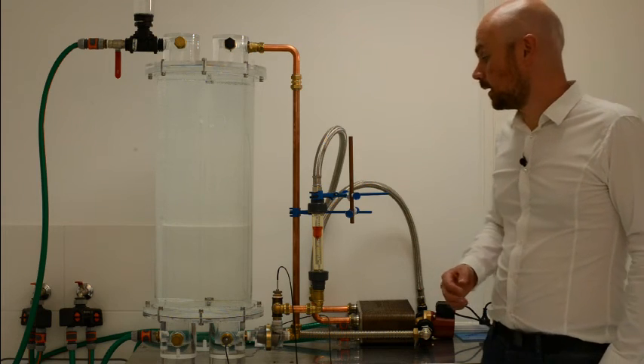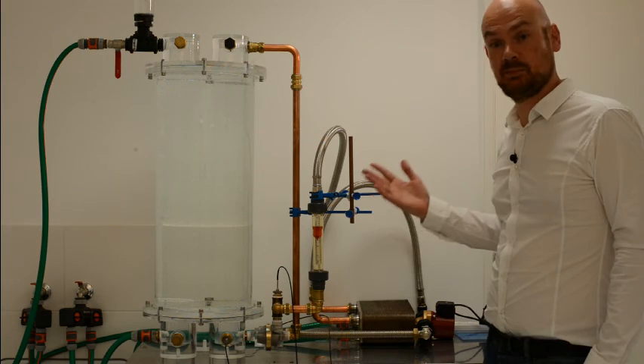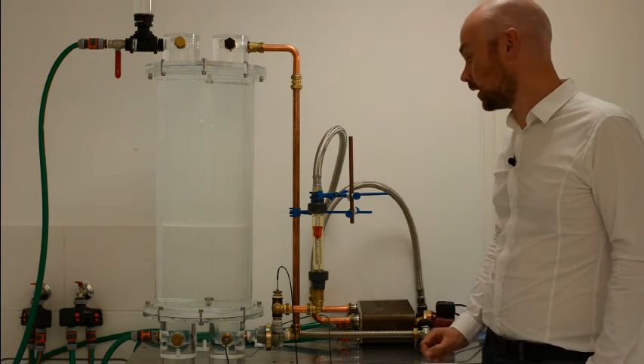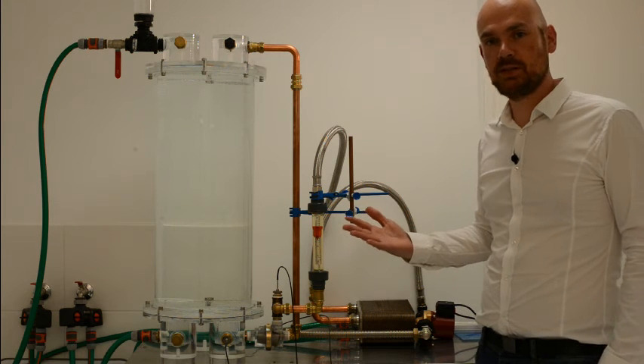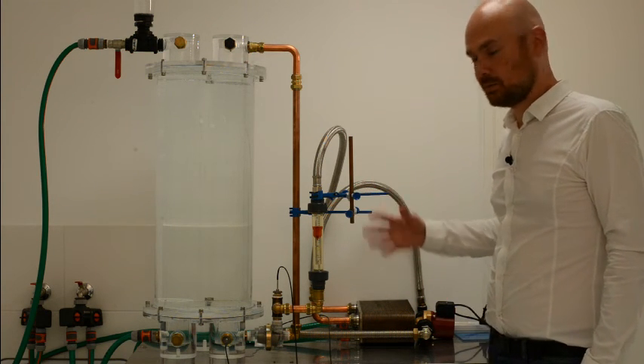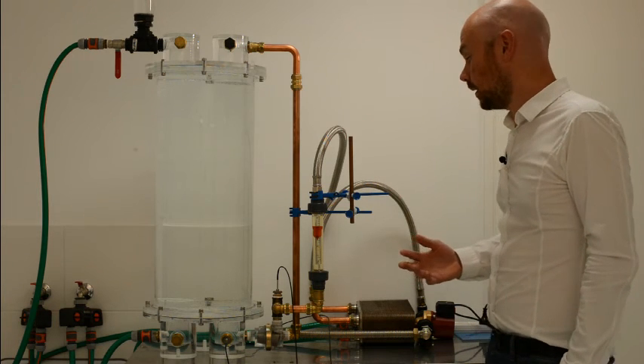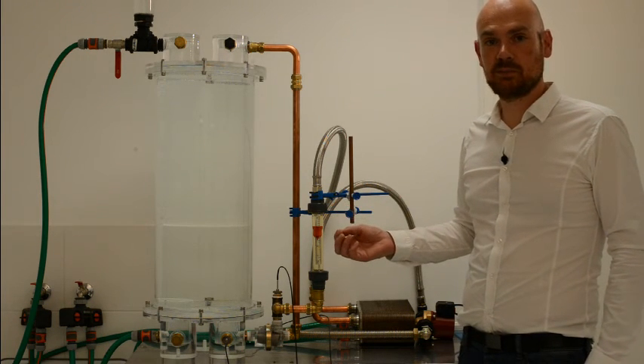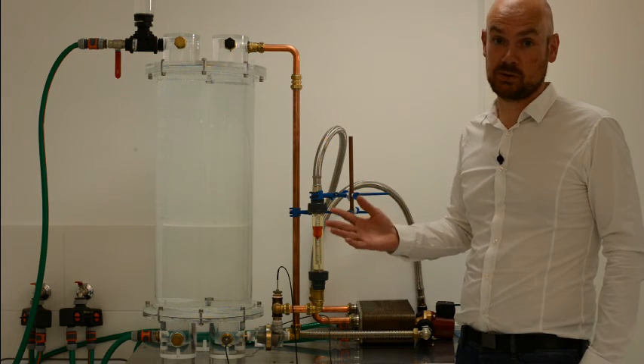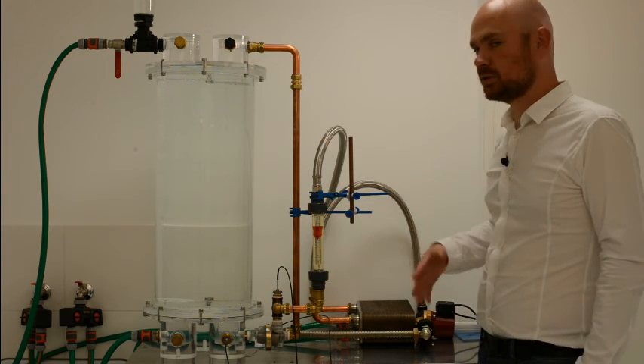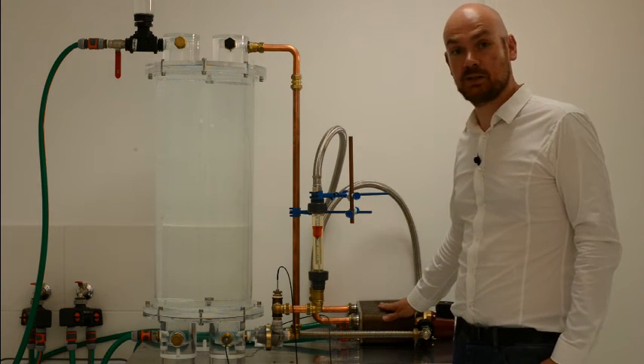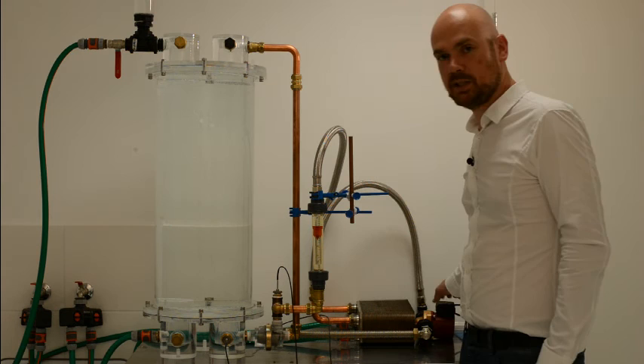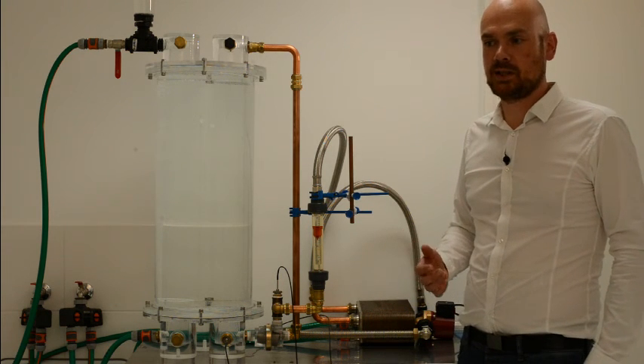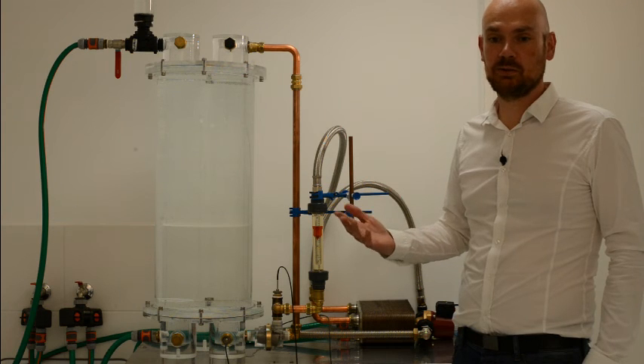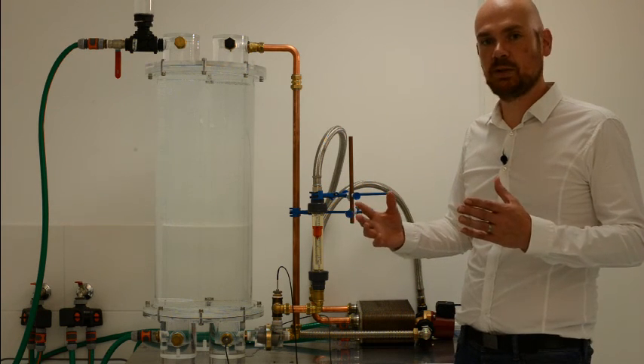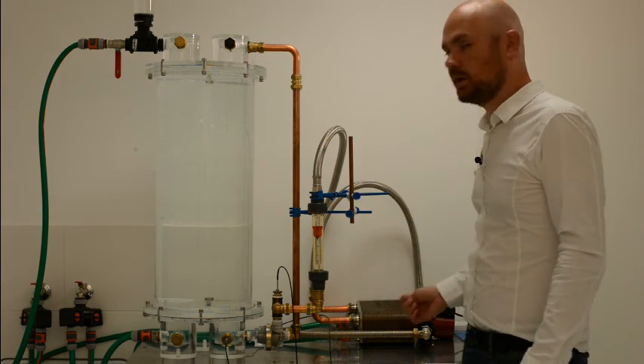So now that we have seen how the valve works and how well it works in acting as a one-way valve for heat flow, or heat diode, I want to tell you a bit more about an example of an application for this valve, which is very similar to the way it is set up here. That application is to create a solar system where you no longer need any differential controller or any controller at all. In such a solar system, this heat exchanger would represent the solar panel, and this pump would be a circulation pump driven by a small PV panel, which would then drive a DC pump whenever the sun is shining. So the pump will run whenever the sun shines.